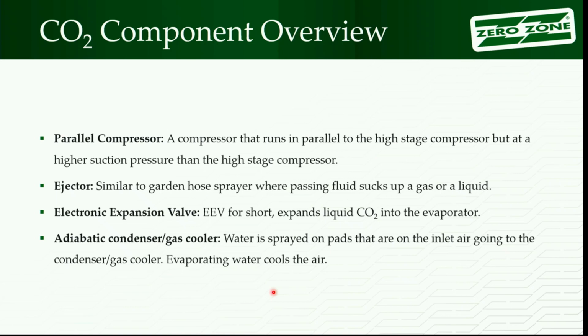So that's what the parallel compressor is doing. It's processing the gas that's coming out of that high-pressure valve, coming out of that tank, and pushing it back up to the gas cooler. So it doesn't have to take a pressure drop and take a bigger step with it. And then there's some limitations. I mean, you can put a lot of parallel compressors in, so you have a lot of turn down. The reality is, from a cost standpoint, they get to a certain point where the parallel compressors are done. They're going to just shut off and cycle on and off. There's not enough gas to keep them up and running.